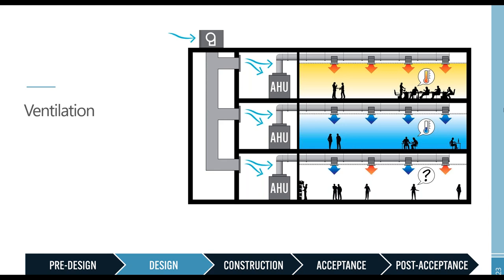This happened in a retro commissioning project for an office building in Washington, D.C. In order to improve indoor air quality, the building had just upgraded their rooftop ventilation fans to increase the volume of outside air being delivered into the building. Typically, we recommend a dedicated outside air unit to treat this incoming air, especially if there's an exhaust air flow stream where we can steal some energy from via an energy recovery wheel and thus increase the efficiency of the project. However, on this specific project, this option wasn't in the budget.